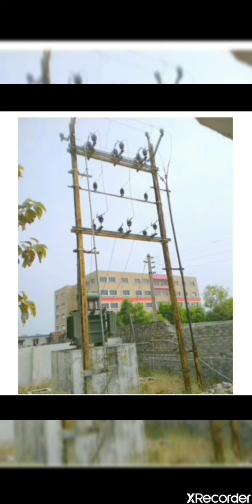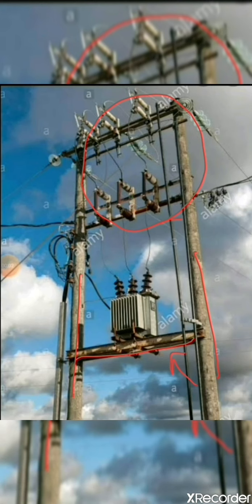The two pole structure is made up of poles with channels and associated accessories. These are all called the accessories, creating an H type pole configuration. And here you can see it is creating an H type pole configuration to locate the distribution transformer at a certain minimum height from the ground level to meet the ground clearance.